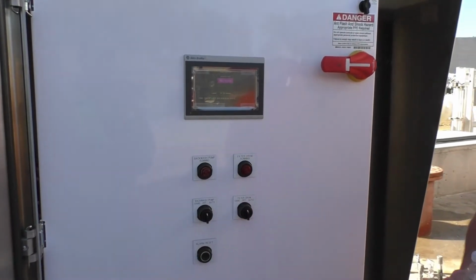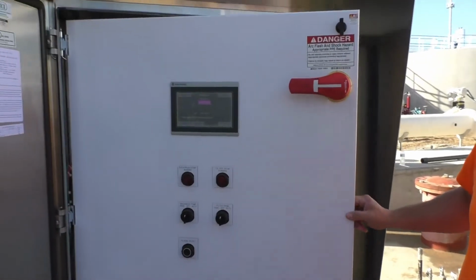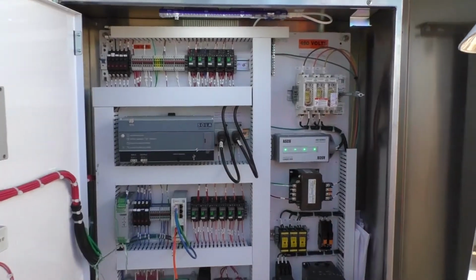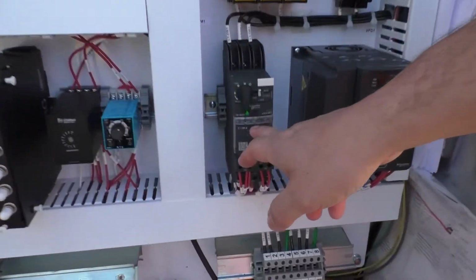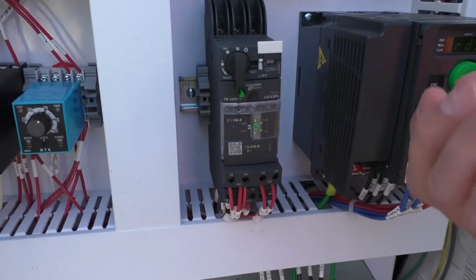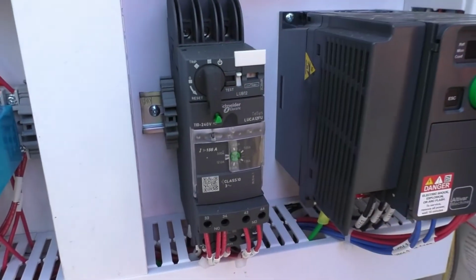So if you ever do get a backwash pump fail or hot backwash pump, this is the motor starter right here. It will be at trip. The way you reset it is you turn it down to where it says reset, and then turn it back up to turn it back on.